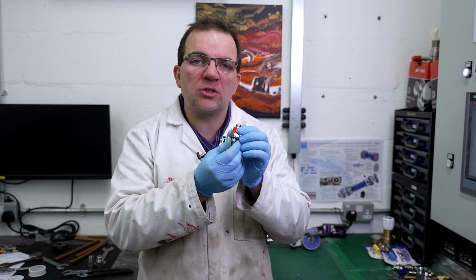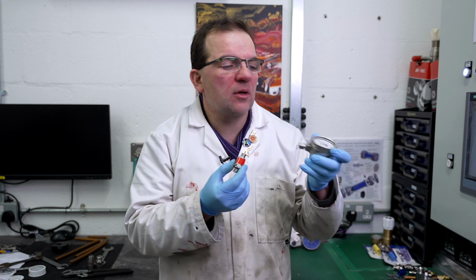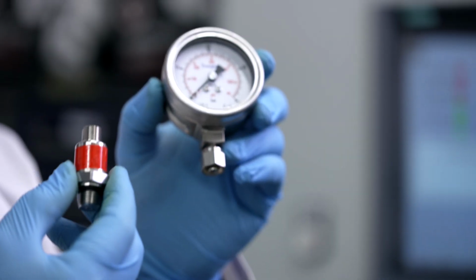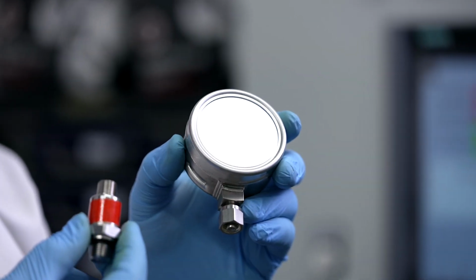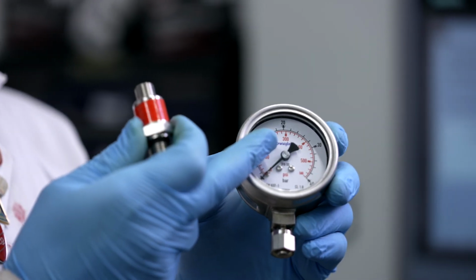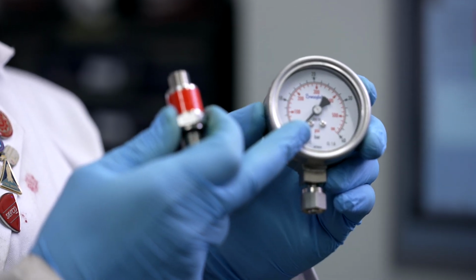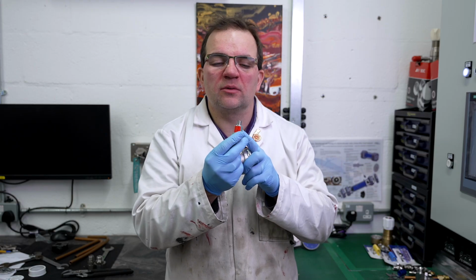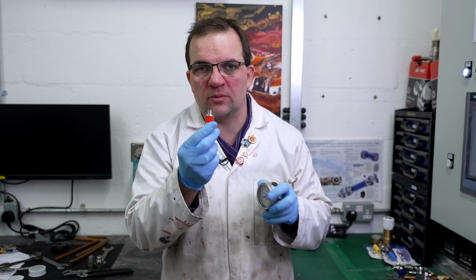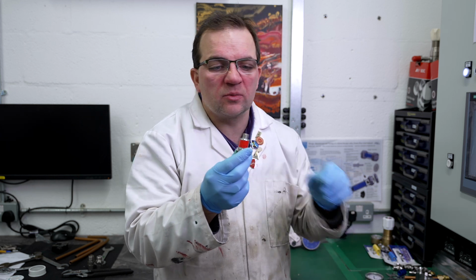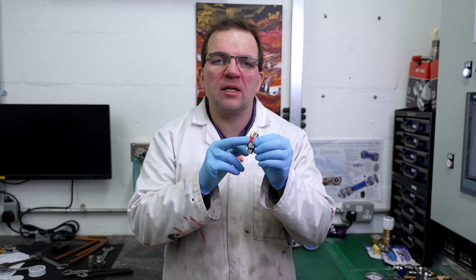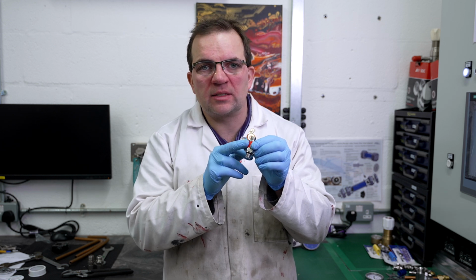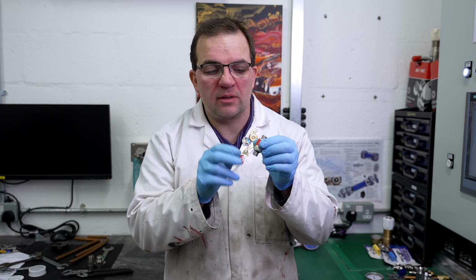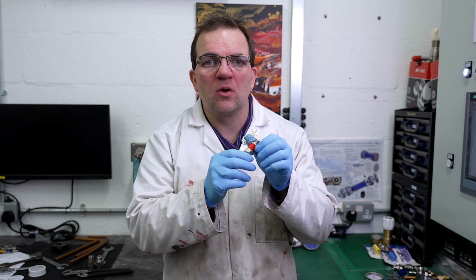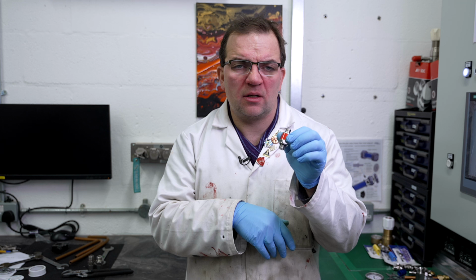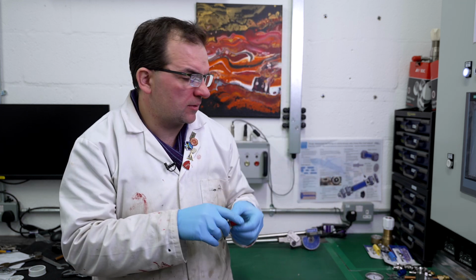Now, in both the digital pressure transducer and the manual gauge, it is very important that you don't over pressurize these systems, because the diaphragms will break and then you could effectively blow off the front of the gauge here, or blow up the internals of the housing in the digital pressure transducers. Saying that, with the digital pressure transducers, although you'll destroy the insides, they do have an ultimate pressure rating as well, so you might be lucky. But don't run these at the maximum. Always go for about 60-70% of their maximum value as a good rule of thumb.